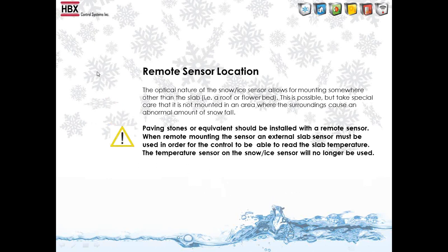So one of the big things about this sensor technology is you can remote mount it. What that allows us to do is you don't necessarily have to put the SNO-0110 sensor in the slab. You can put it in a flower bed, you can put it beside the driveway, we've had some people put it on a roof. But all you have to do basically is have a remote slab sensor in the slab. So that's just basically the slab thermistor would have to be in the slab, so that we can still know the slab temperature.